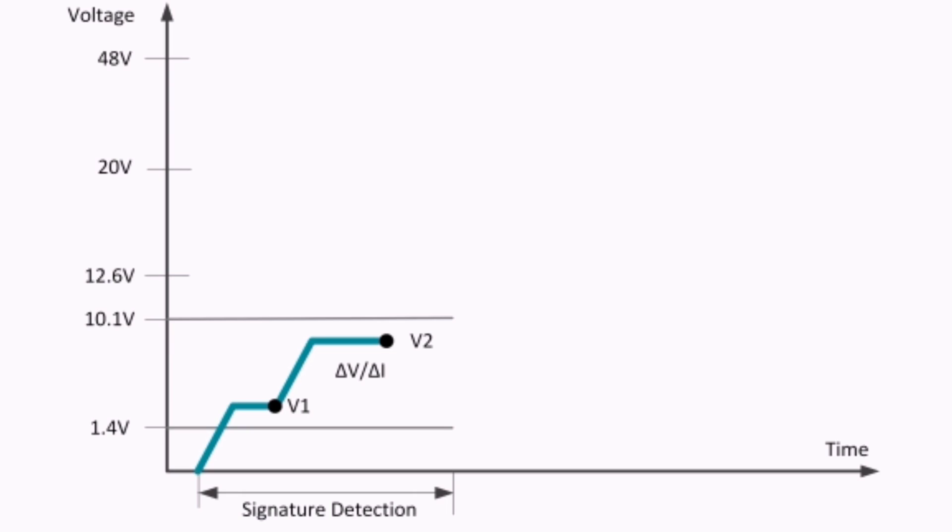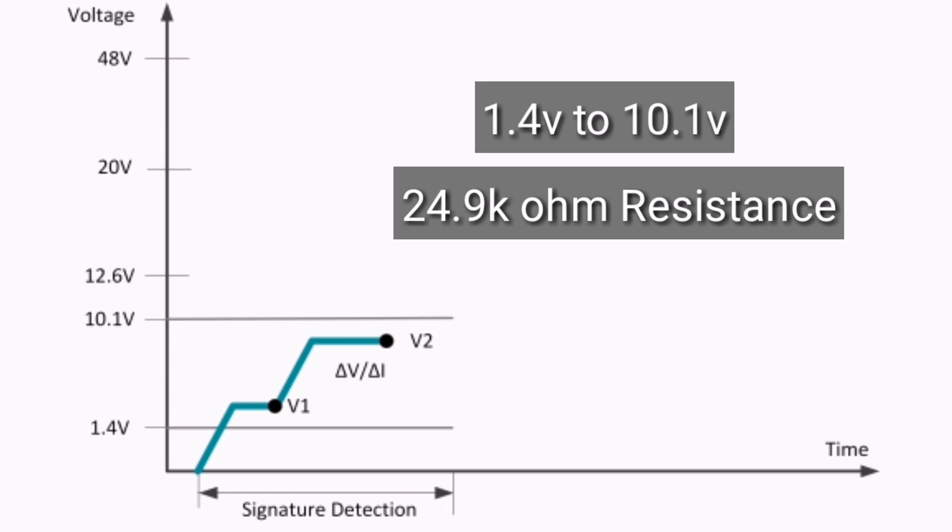The first step in the process is signature detection. Signature detection uses a low voltage of 1.4 volts to 10.1 volts to detect a characteristic signature of IEEE-compatible powered devices using a 24.9 kiloohm resistance.